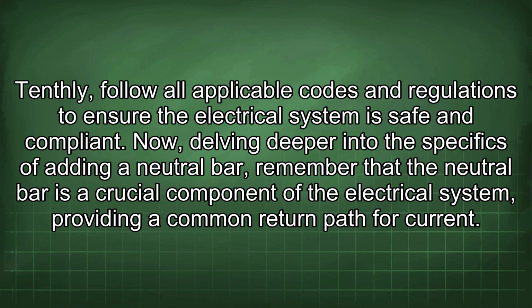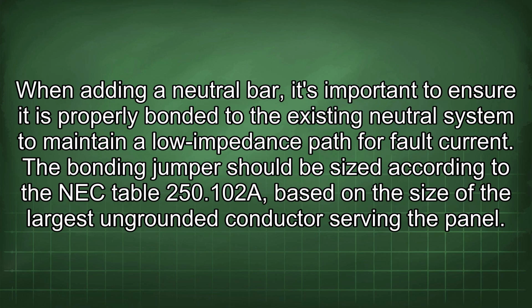Now, delving deeper into the specifics of adding a neutral bar, remember that the neutral bar is a crucial component of the electrical system, providing a common return path for current. When adding a neutral bar, it's important to ensure it is properly bonded to the existing neutral system to maintain a low impedance path for fault current. The bonding jumper should be sized according to NEC table 250.102A based on the size of the largest ungrounded conductor serving the panel.